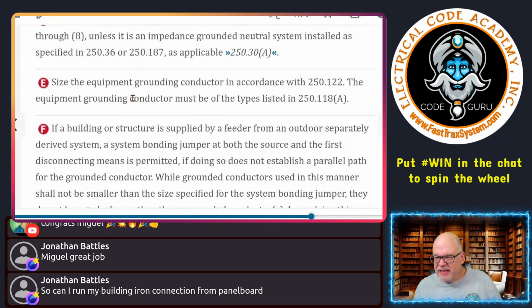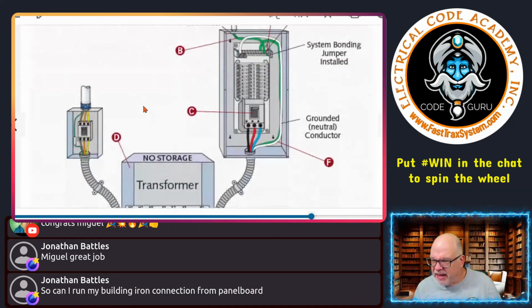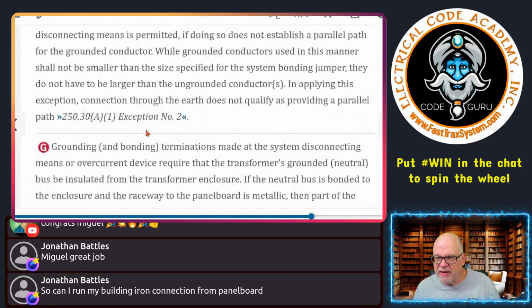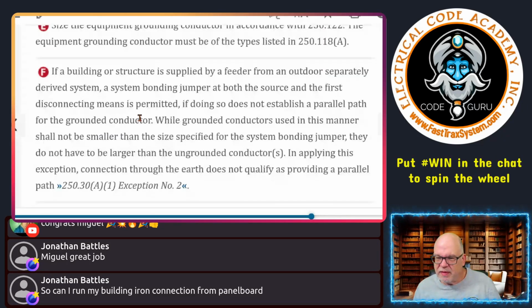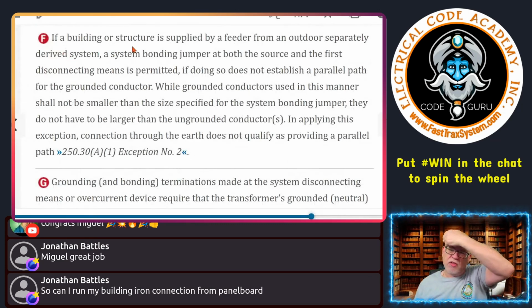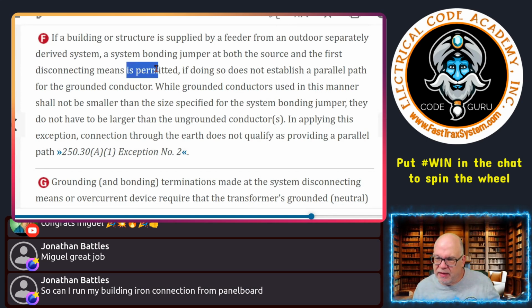Okay, F. What is F? F is right here. All right, what's F talking about? It says, if a building or structure is supplied by a feeder from an outdoor separately derived system, a system bonding jumper at both the source and the first disconnecting means is permitted.